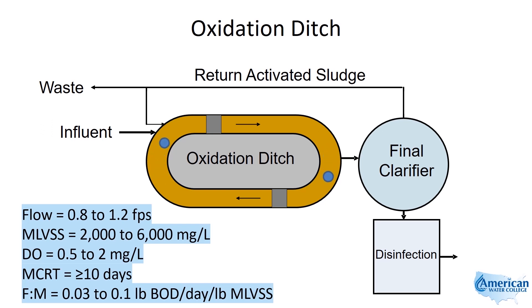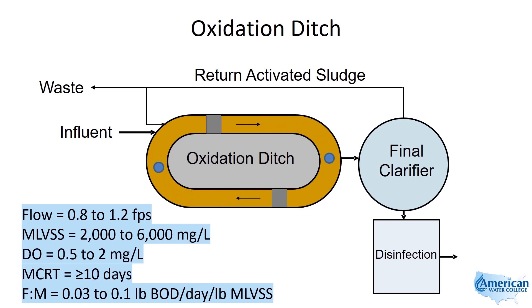The rotors act as the aeration devices and they maintain the flow between 0.8 and 1.2 feet per second, which prevents the mixed liquor volatile suspended solids from settling out. However, it does allow the heavier solids to settle out, so grit will settle in the bottom of the ditch.